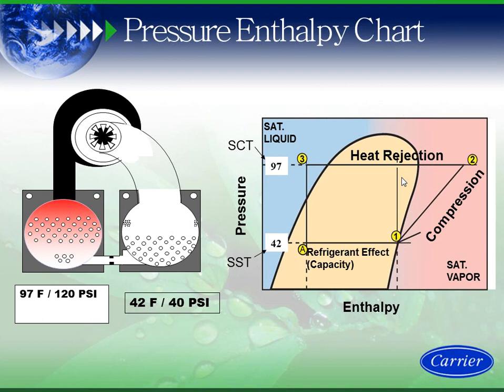Most of the time, however, it's not a design day. This pressure enthalpy chart shows a design day. However, in most cases we're going to be able to have at least 70-degree entering condenser water temperatures. If I get 70-degree entering condenser water, I'm going to assume approximately 80-degree leaving water, with a 2-degree approach, so I would have an 82-degree saturated condensing temperature. Because I'm able to deliver colder water through the tower, I'm now reducing the lift on the chiller. That's a key piece.